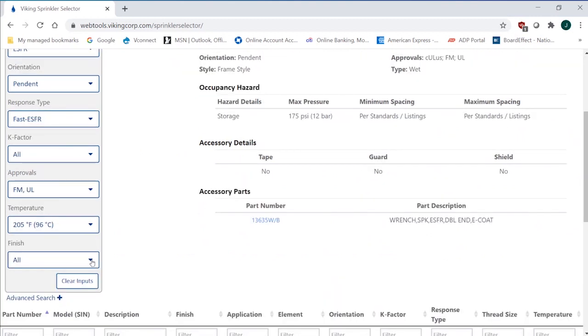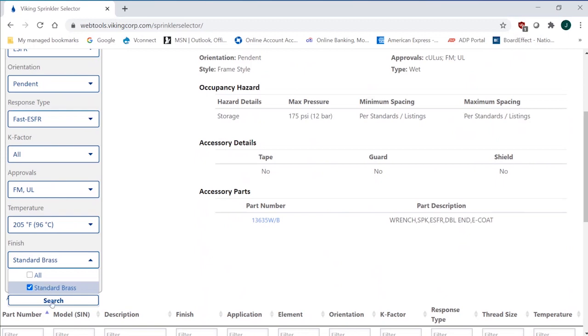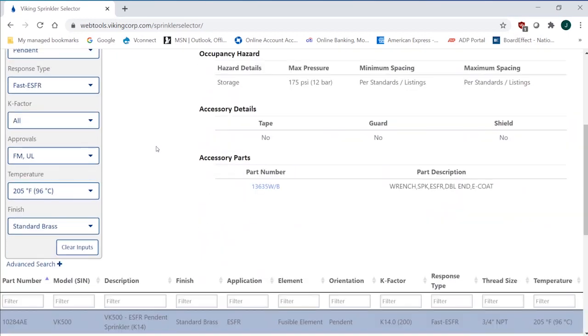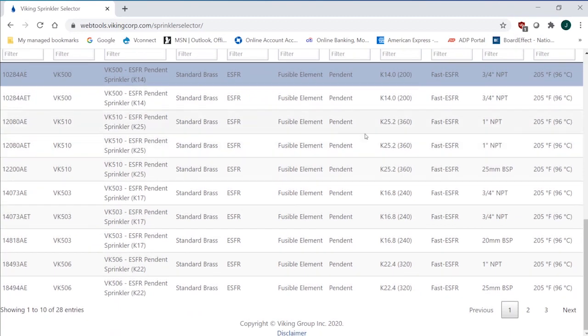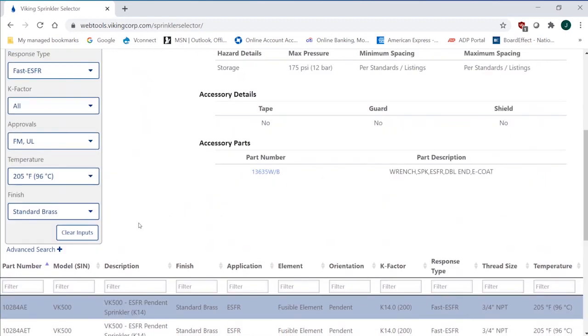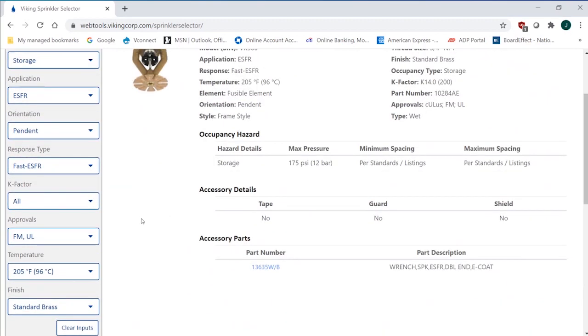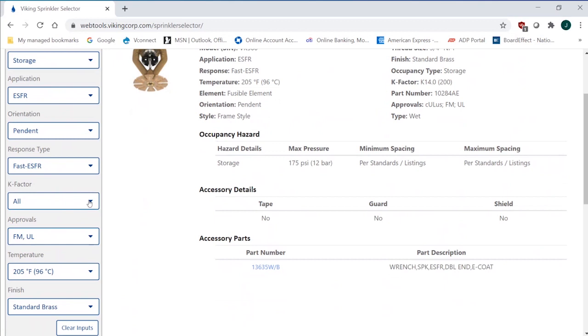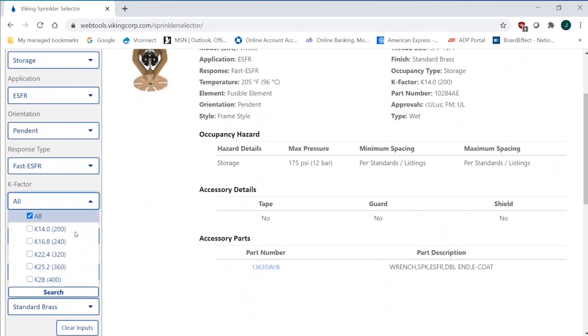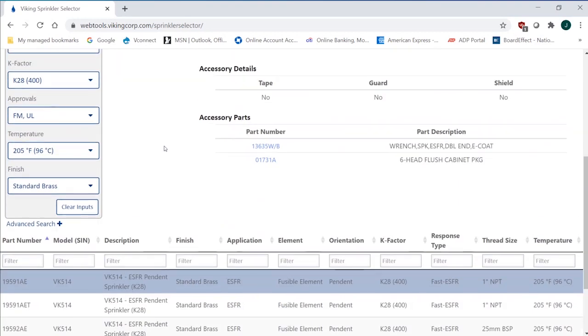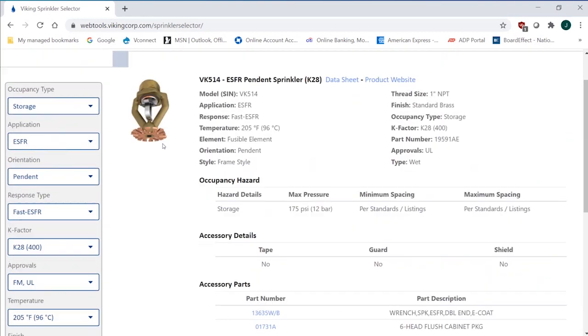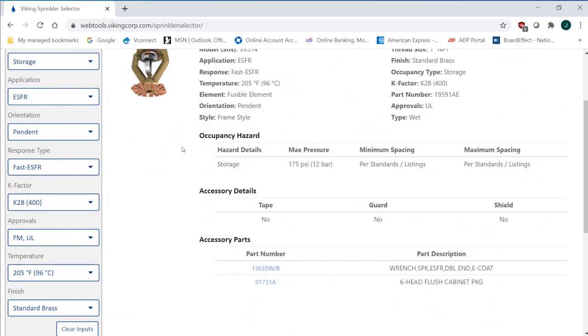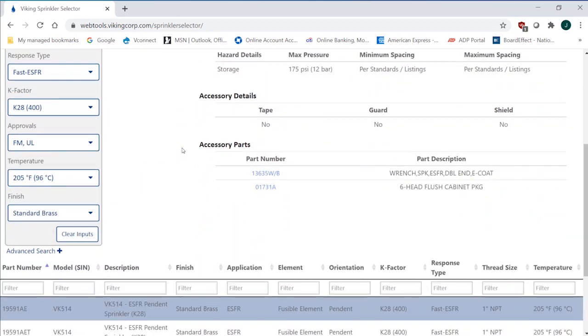Finish really doesn't matter. Standard brass on an ESFR, that won't change anything. And then I'm going to get down to the point where I've got to pick a K-factor, and that's going to be your design application based on how high your ceiling is. If I had a 50-foot ceiling right now that I was looking at, I would definitely pick the K-28. It's just got some new applications with Factory Mutual on the 50-foot application with a 9-sprinkler design that's really great on hydraulics with a 3x3x3 on the calculation area.